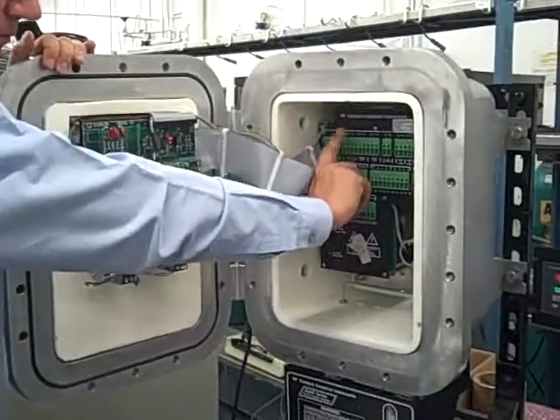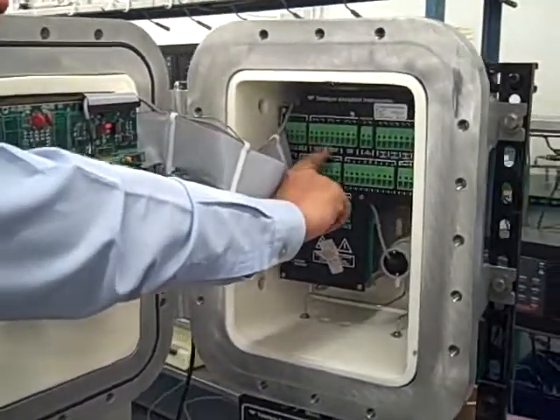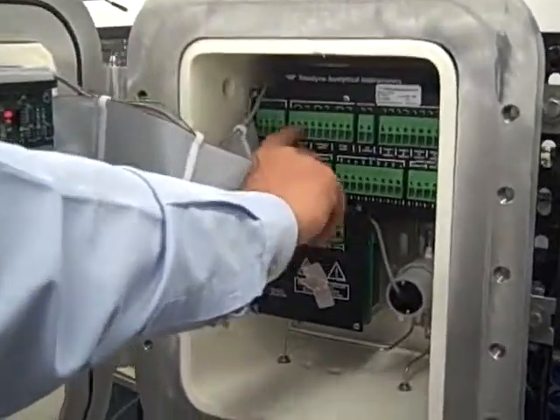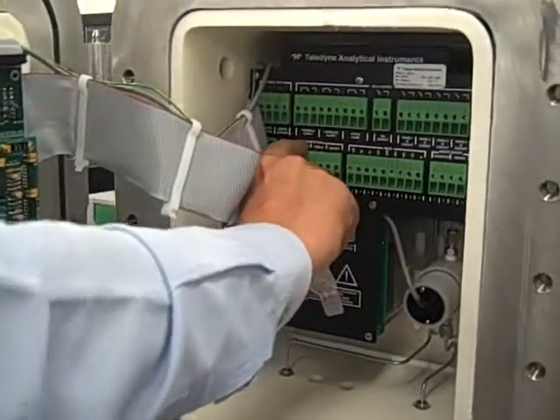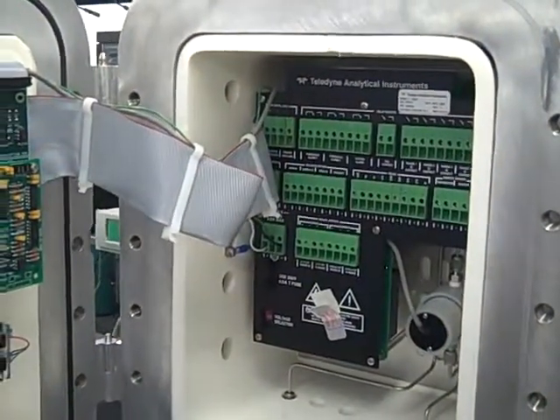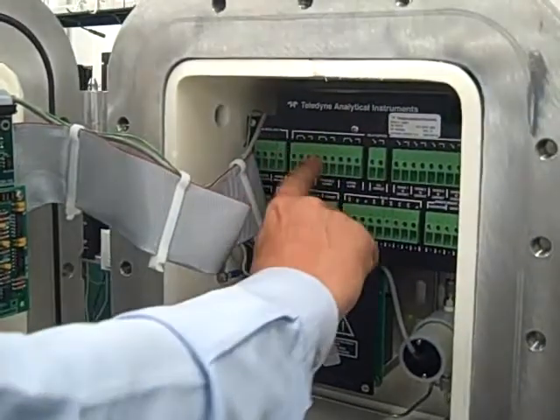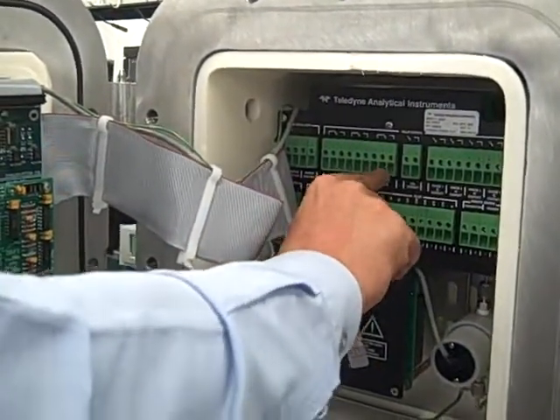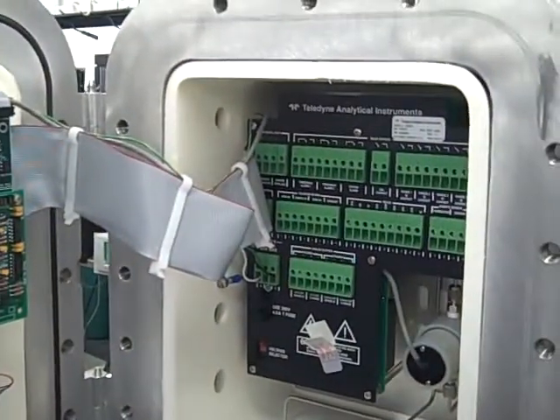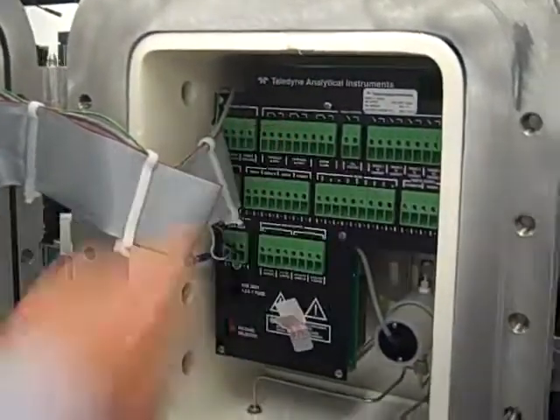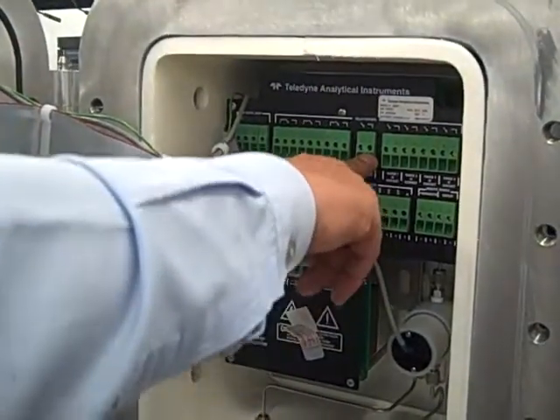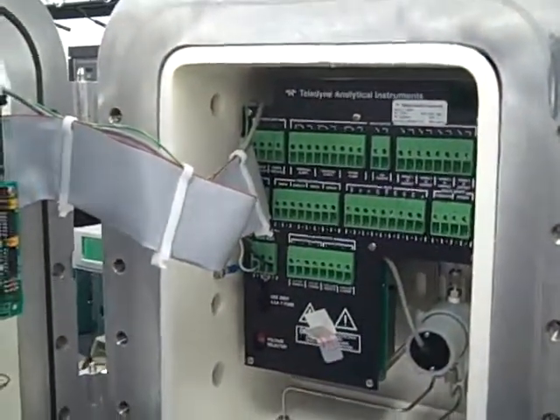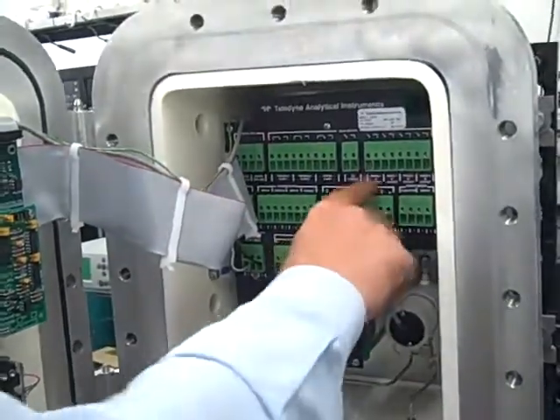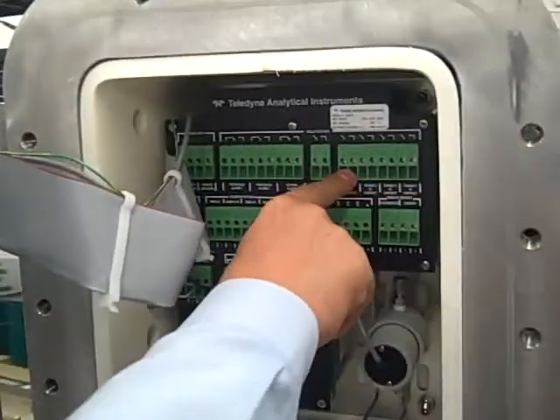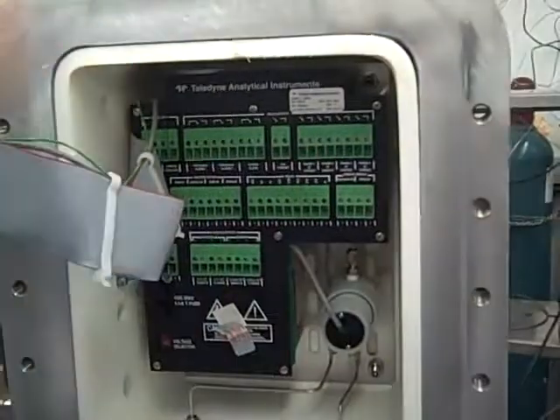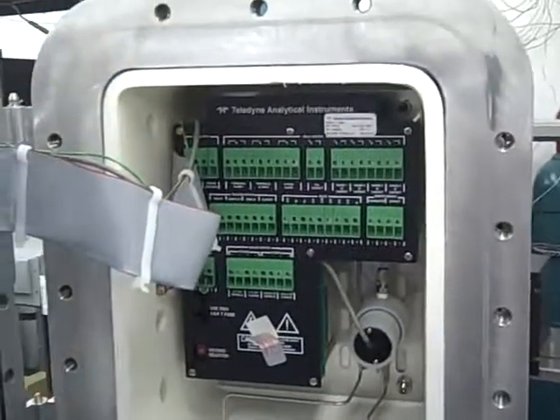We also have programmable alarms, two alarms, alarm 1 and alarm 2, which are shown here to connect to. They can be configured as fail-safe, non-fail-safe, latching, and non-latching, as shown on the silk screen. There's also a system failure alarm that can be configured the same way. There's a calibration contact, which is a relay contact that you can connect to your process control computer that will tell you if you're in the calibration mode or not. We have 4 range identification contacts to tell your computer which operating range the unit is on.